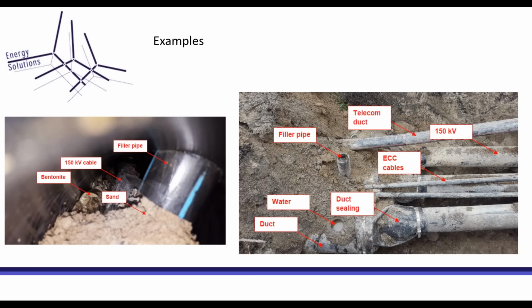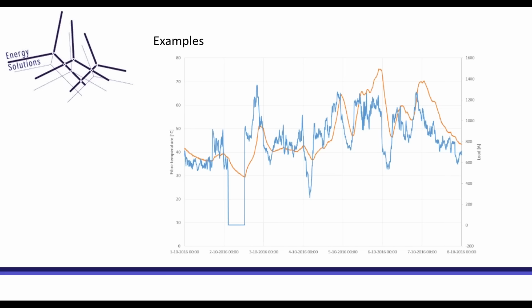Normally when you install cables in ducts which are placed in air, you have some kind of convection, but in this case there was only a small layer of air, which is a very good insulator. So that was quite a thermal problem in this connection. And here you can see the load on the cable at that time. In orange you see the fiber temperature, and in this case the 75 degrees fiber temperature corresponded to the maximum conductor temperature, 90 degrees. So at this point they had to take measures to limit the cable to prevent any damage.